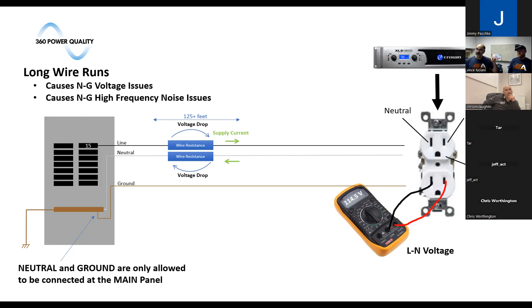Another way is just through RF energy, EMI, RFI energy that's in the air. Think about Romex wire running for hundreds and hundreds of feet around the house. It's basically an antenna at that point, and you're picking up a lot of noise. The National Electric Code states very clearly that there's only allowed to be one neutral to ground bond in a system, and that is in the main breaker panel. That's the only spot, except if you use an isolation transformer.